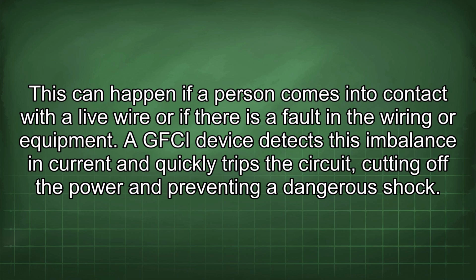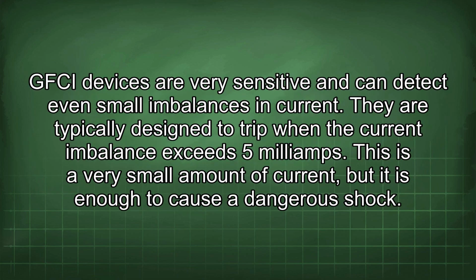A GFCI device detects this imbalance in current and quickly trips the circuit, cutting off the power and preventing a dangerous shock. GFCI devices are very sensitive and can detect even small imbalances in current. They are typically designed to trip when the current imbalance exceeds 5 milliamps. This is a very small amount of current, but it is enough to cause a dangerous shock.